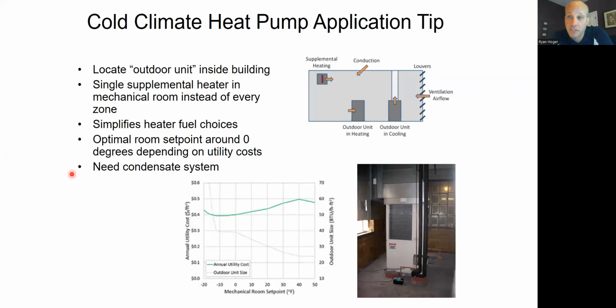If you don't have anything out there now and you need to add heating to all those zones, that becomes very costly, right? So in those cases, this is a trick you might want to consider. I don't remember where I got this picture from, but the first place I saw this was one of the mechanical contractors in Wisconsin did this at their own office building. At first I was baffled, like, what the hell are you doing? And then I was like, this is actually quite brilliant. So instead of putting heaters out in all their zones, what they did is they put their heat pump inside the building. Instead of rejecting heat to the outdoors or getting it from the outdoors, they get it from a room and reject the heat to the room or pull it from outdoors.